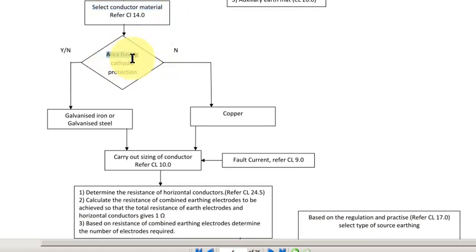If the area is not having cathodic protection, go for copper. If the area is having cathodic protection, you can either go for galvanized iron or galvanized steel.